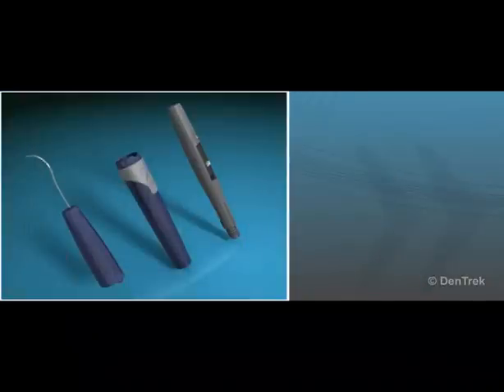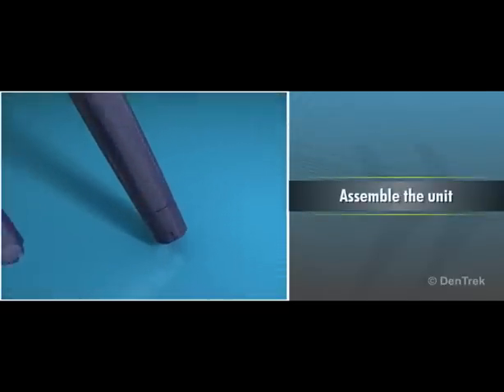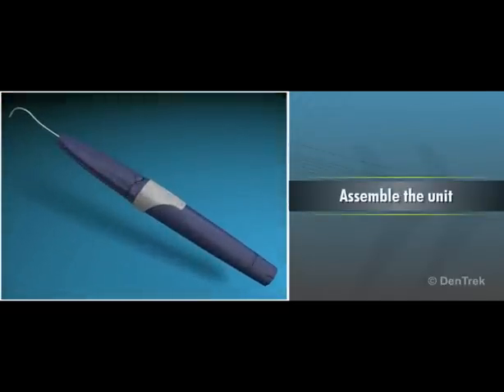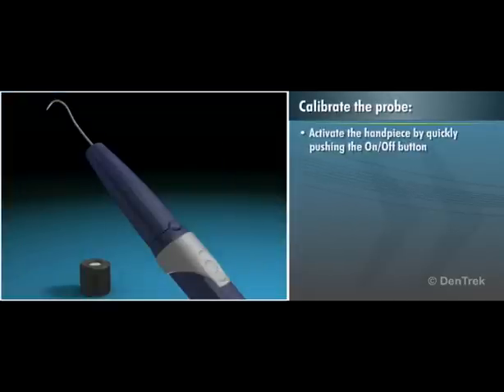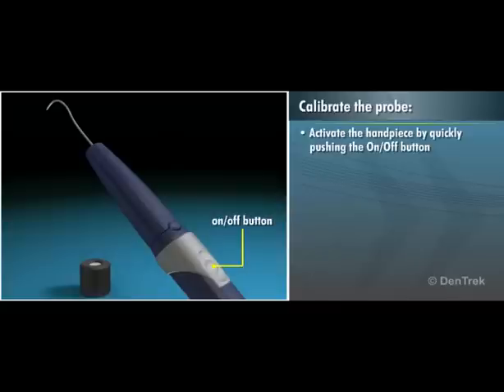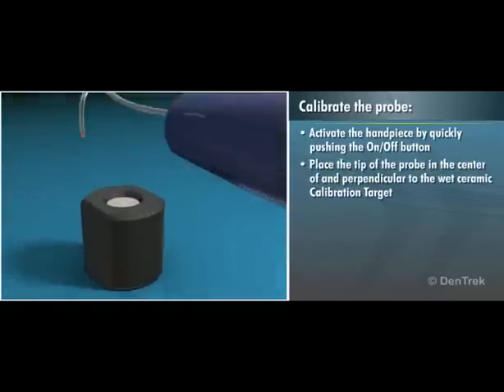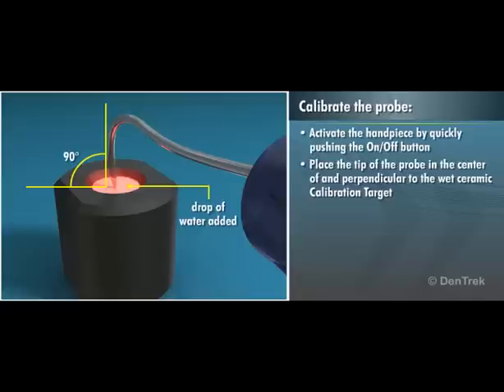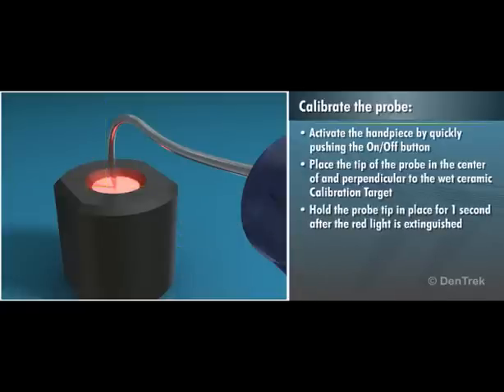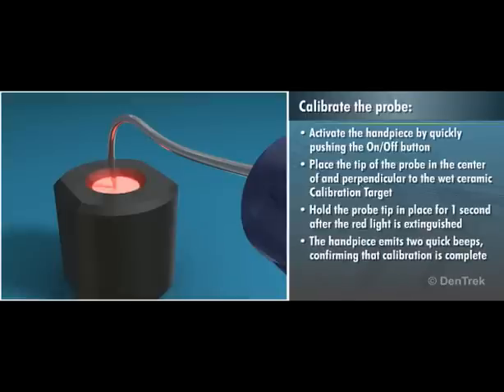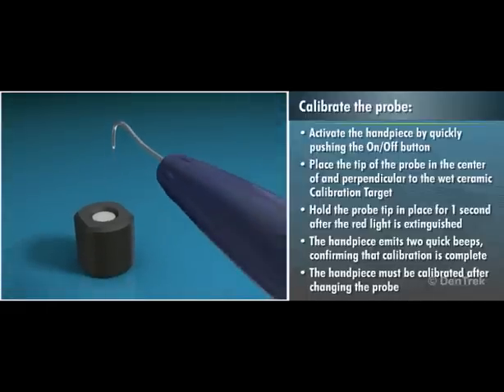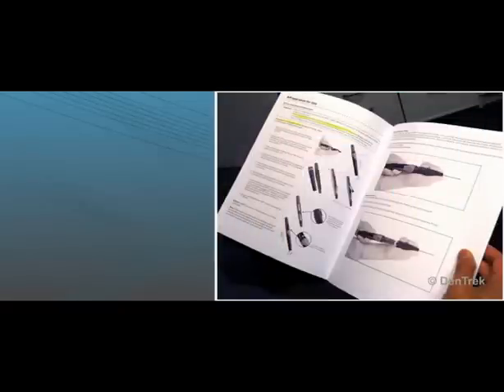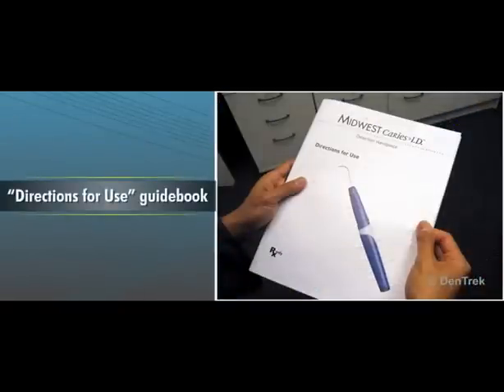To use the Midwest Caries ID Detection Handpiece, first assemble the unit. Once the unit is assembled, the probe must be calibrated. To calibrate, activate the handpiece by quickly pushing the on-off button. The handpiece will emit steady beeps, indicating it is in calibration mode. Place the tip of the probe in the center of and perpendicular to the wet ceramic calibration target. Hold the probe tip in place for 1 second after the red light is extinguished and the handpiece emits 2 quick beeps, confirming that calibration is complete. The probe must be calibrated after changing the probe. For complete assembly and calibration directions, please refer to the Directions for Use guidebook.